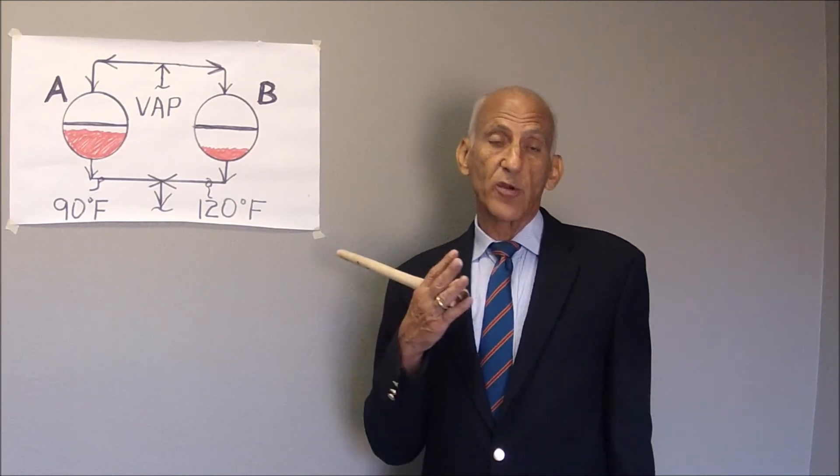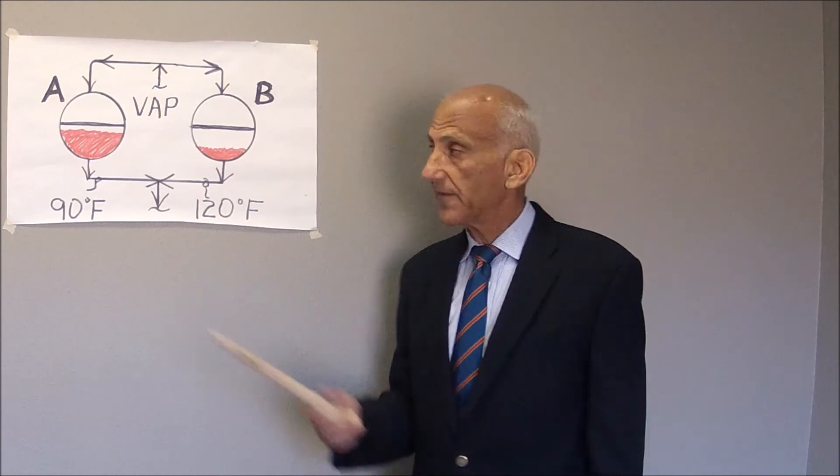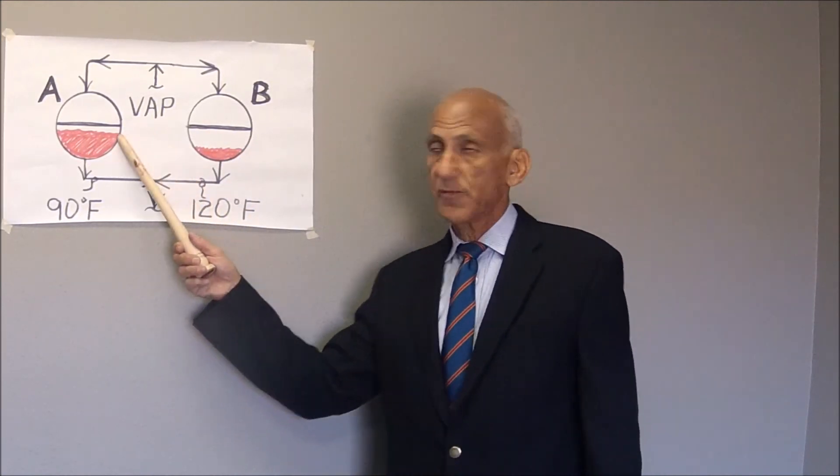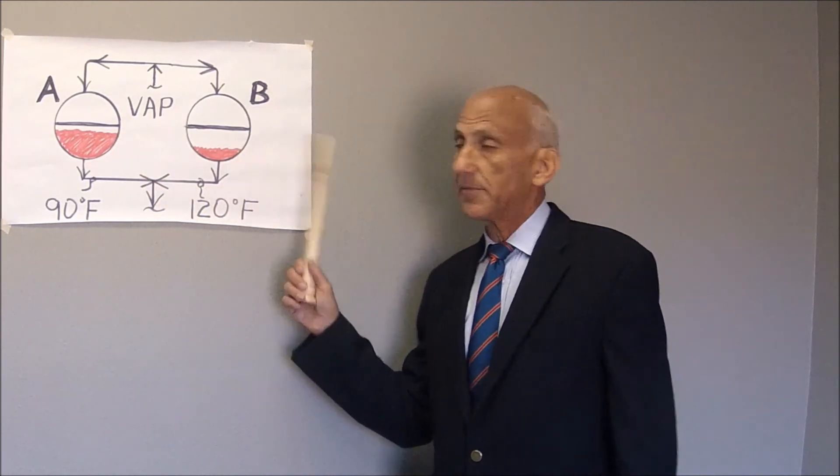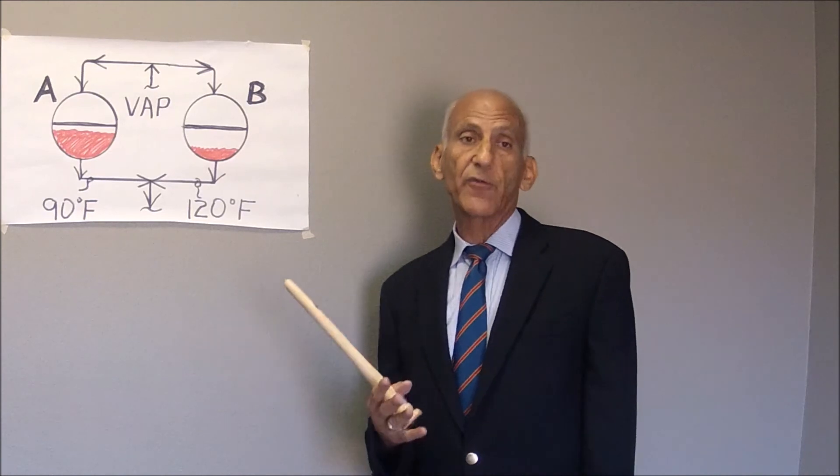that then would correspond to a liquid vapor interface inside the condenser. And as you can see, that interface would be higher in A than B, and that is the way I would do it in the field with my infrared temperature gun.